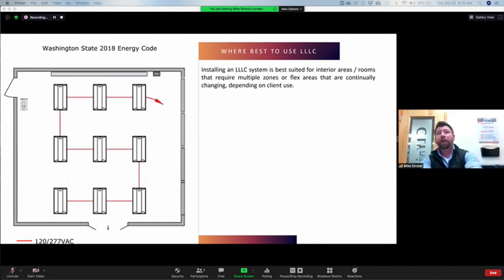So let's look at a classroom with large windows along the right-hand side. There's a room entry switch and a whiteboard at the front of the class with a touch screen. You can see the little TS there at the top right-hand side. Using distributed relay controls like, say, nLight, a Wattstopper, a Hubbell, can you tell me how many zones or relays will be required to meet code?